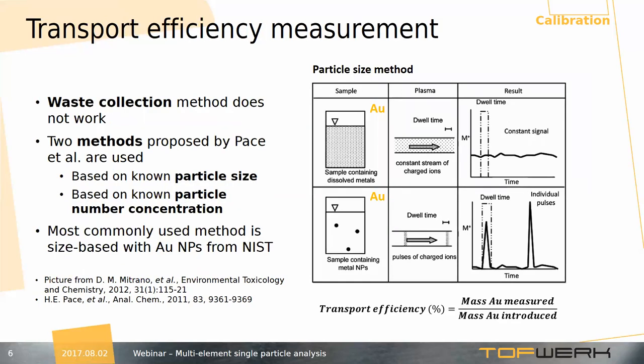The problem with this approach is that we don't know how much of our solution is being introduced into the plasma, because transport efficiency of the sample introduction system is very dependent on operating conditions and has to be measured. The most straightforward way is waste collection — you weigh how much solution was introduced and how much goes into the waste and calculate the mass flux. However, this method unfortunately doesn't work and usually results in underestimation of particle sizes.